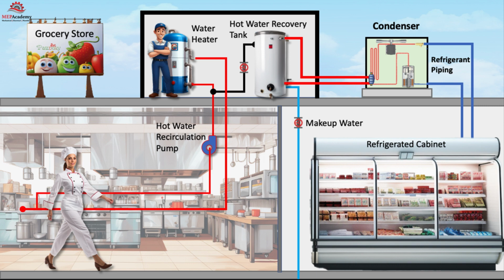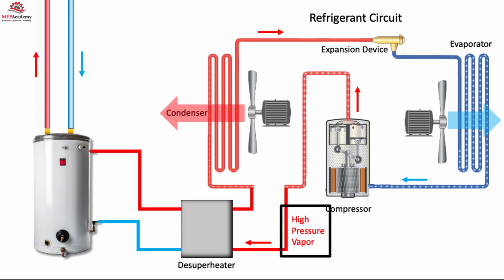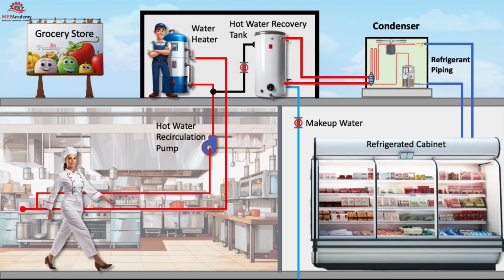1. System setup. The desuperheater is typically integrated into a heat pump or air conditioning system, and consists of a heat exchanger. 2. Heat extraction. When the air conditioning or refrigeration system operates, it produces high pressure, high temperature refrigerant vapor. The desuperheater diverts this superheated refrigerant to the heat exchanger.